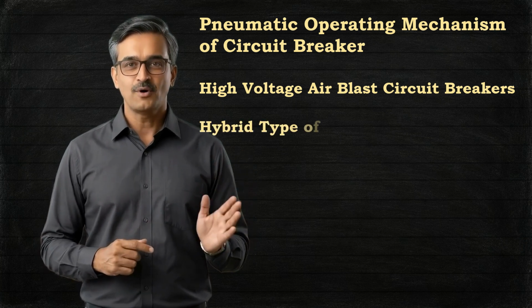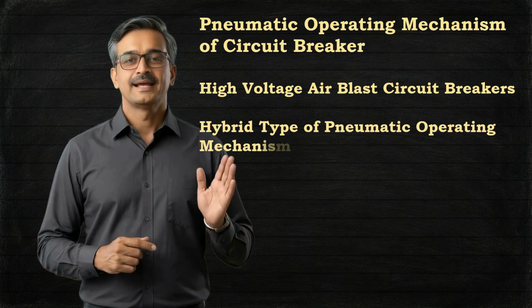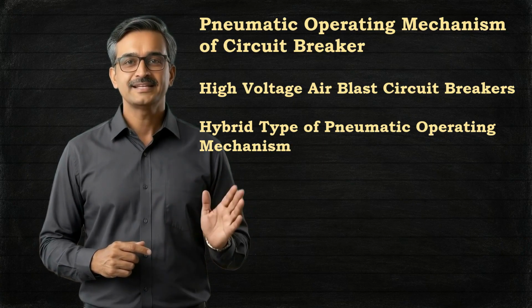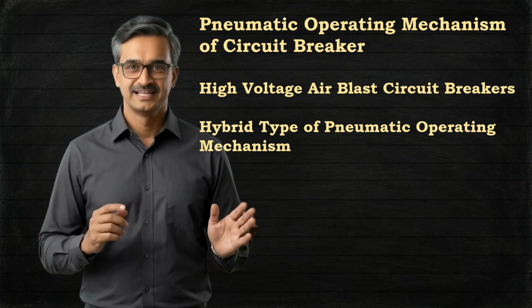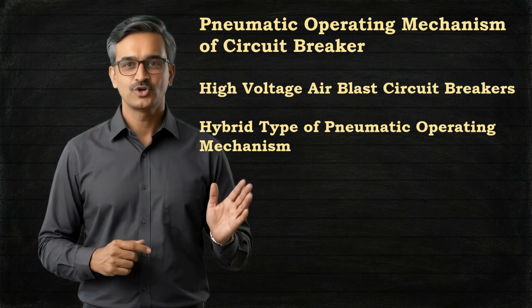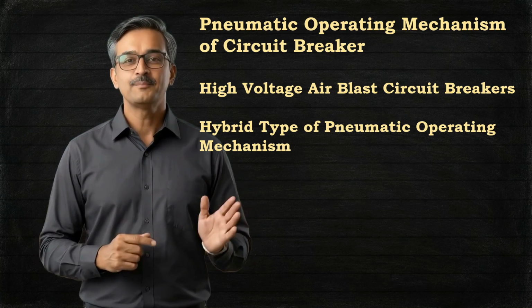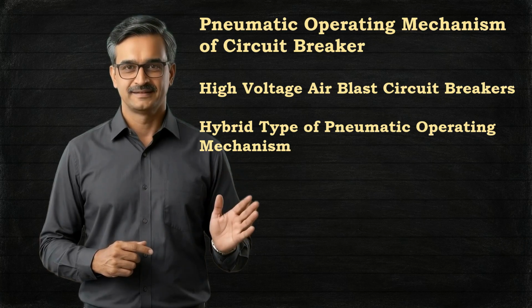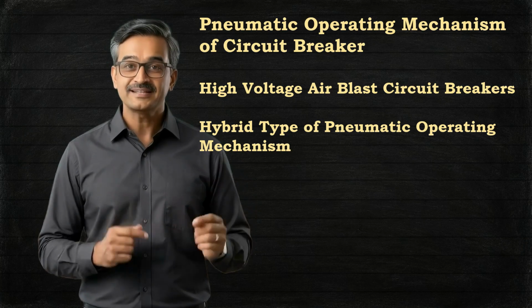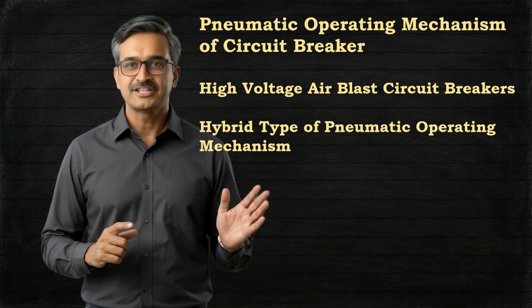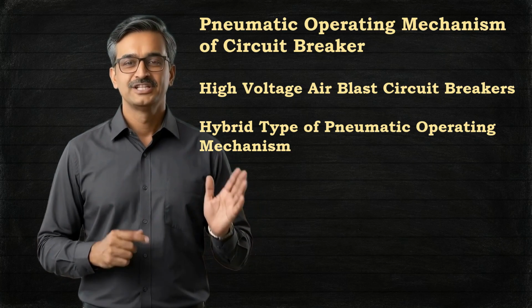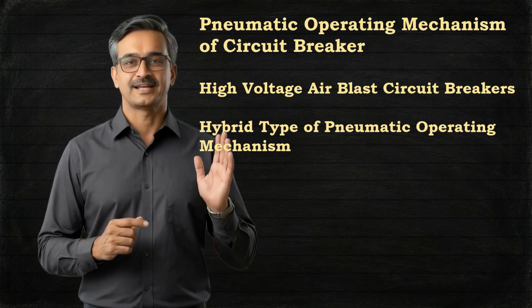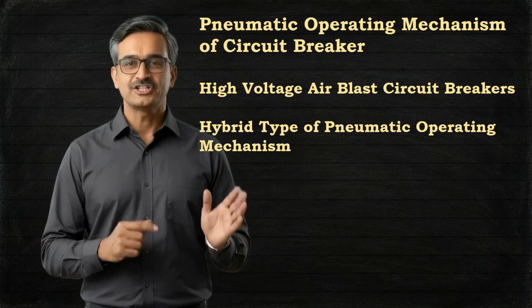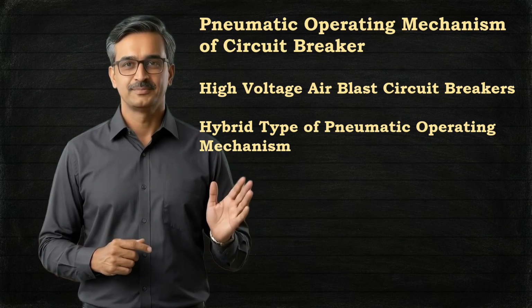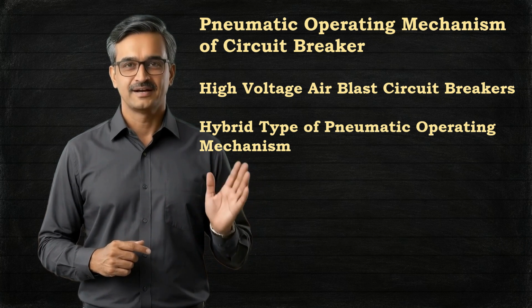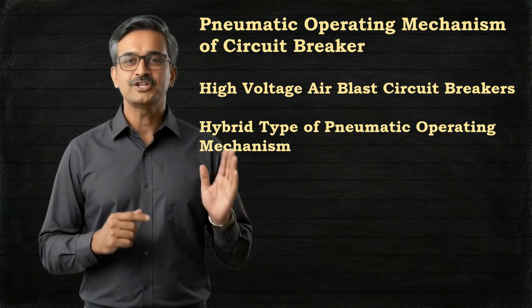A hybrid type of pneumatic operating mechanism is also used. In this mechanism, the closing spring is not charged by a rotating motor. Instead, compressed air pushes a piston, and due to the movement of the piston, the closing spring gets charged. During the closing operation, when the closing spring relaxes, it also charges or compresses the tripping spring, making the circuit breaker ready for the next tripping operation.